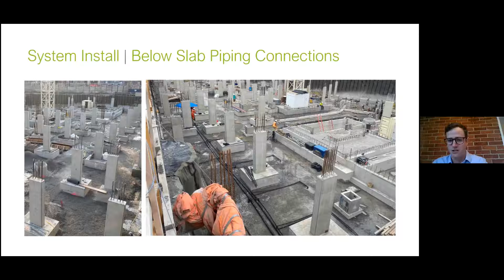In the photo on the right, we now have this initial bedding layer completed, and the horizontal piping runs have started. You can see the smaller 1.5 to 2-inch pipe coming up and connecting in a 90-degree elbow from the wellhead, transitioning to the main horizontal loop piping. Those pipes start as 4-inch pipe and taper down to 3-inch as they approach the end of the runs, running extensively throughout the entire under-slab area. There weren't too many areas without wells in this situation.